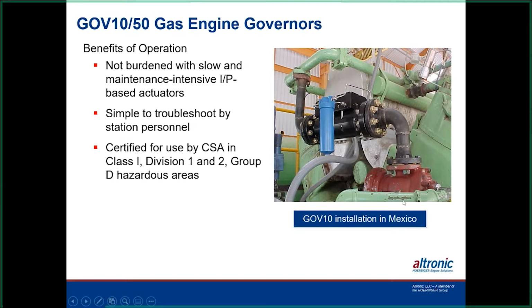And you can see in this picture here where they've got the block and bleed on the valve. So this area in here needs to be at zero pressure, so the valve can go through and recalibrate itself. Again, you can get away with it in some cases, but if you set the valve up right when you're programming it at the beginning, if it senses any kind of high pressure, it won't allow you to start the engine.